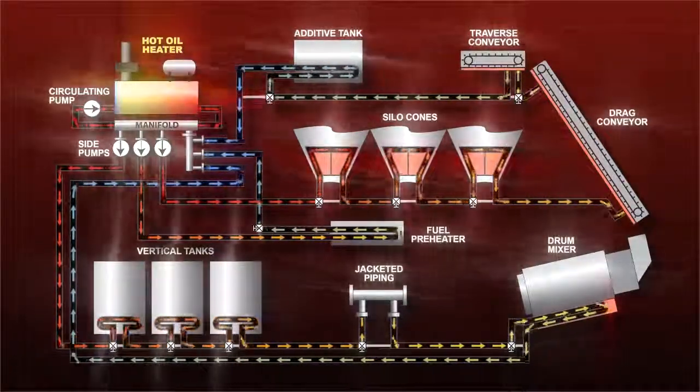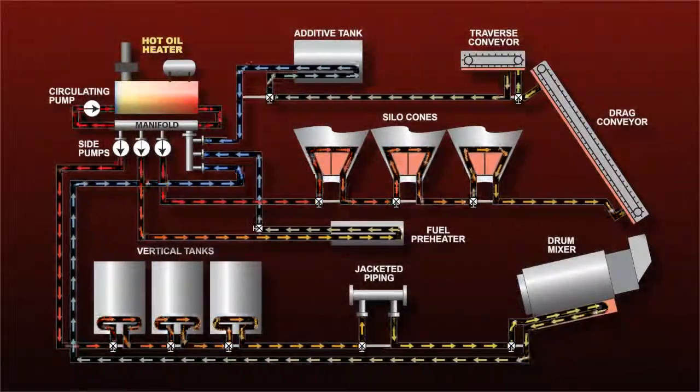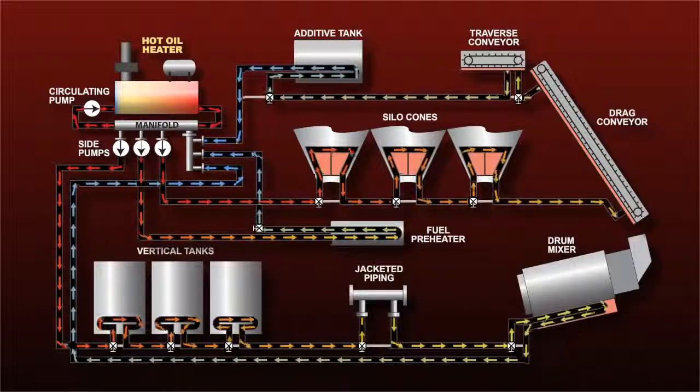Moreover, heater shutdowns are avoided because the circulation pump maintains optimum flow through the heater coil.